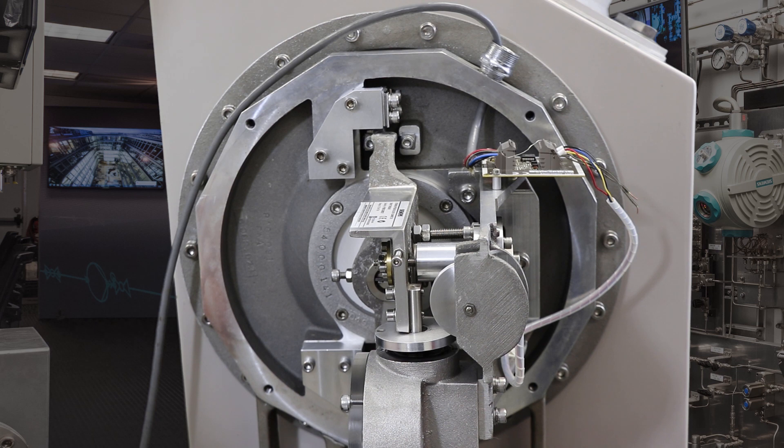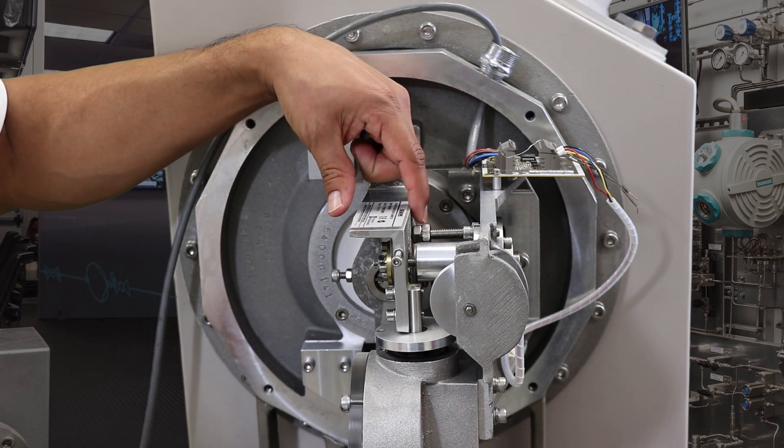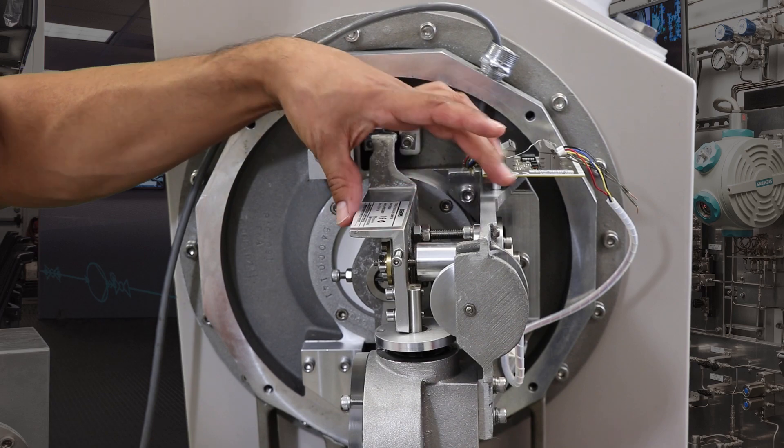Now after inspecting the gaskets, you're going to inspect the overload stop. It has two nuts that allow the unit to bottom out.